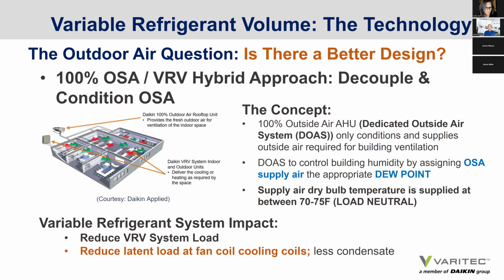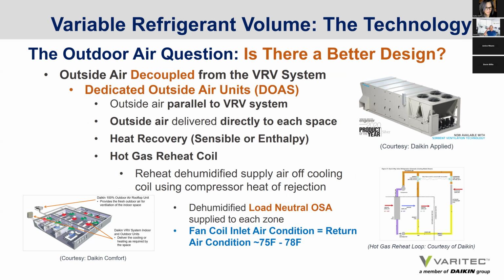And you can provide load neutral air using hot gas reheat from a DX compressor and a DX 100% outside air unit. By doing this, you reduce the variable refrigerant system load. In fact, the technology of our manufacturer will allow you to put a variable refrigerant coil in the 100% outside air unit to ride the outside air demand with varying, modulating refrigerant flow as well. So it's a very attractive solution. And by doing this, we can reduce the latent load at the VRV fan coil units and reduce the mixed air temperature at the cooling coil of those fan coil units.